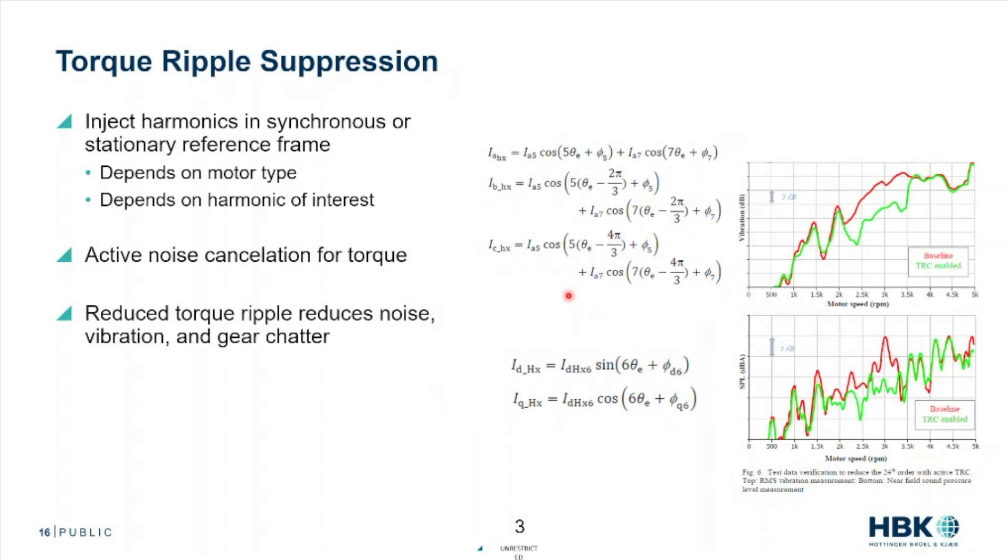Torque ripple suppression: we can inject harmonics at a certain area in the machine, in the synchronous or stationary reference frames, depending on motor type. But it's basically active noise cancellation for torque. If we have a torque ripple, we can inject harmonics into the current to try to eliminate that.